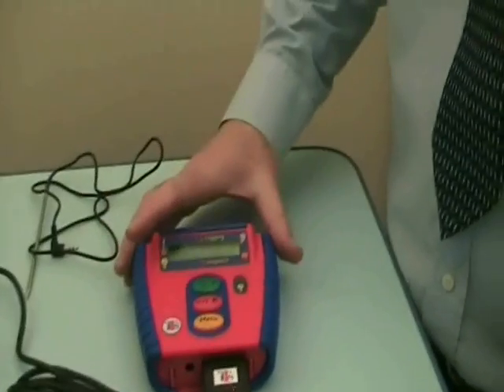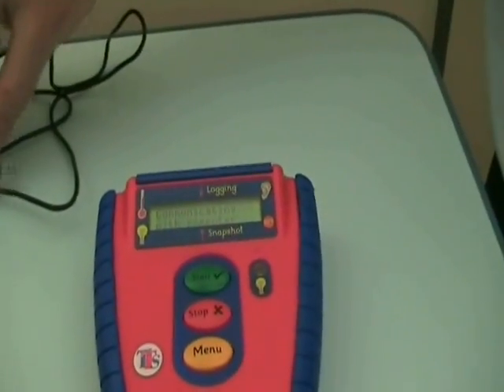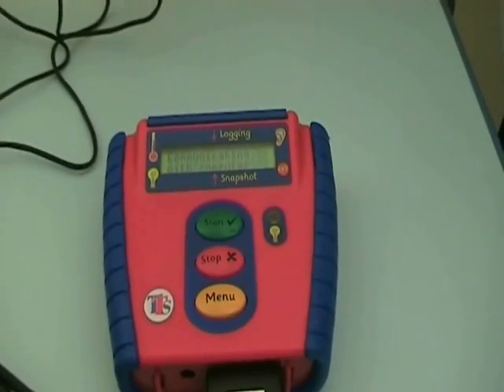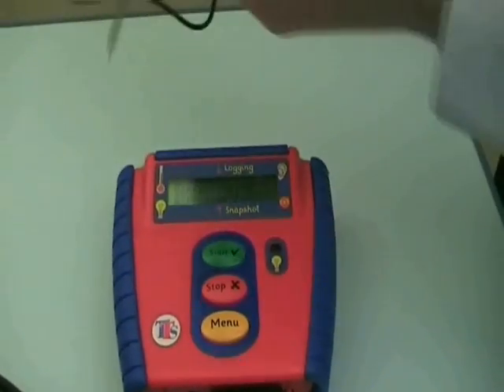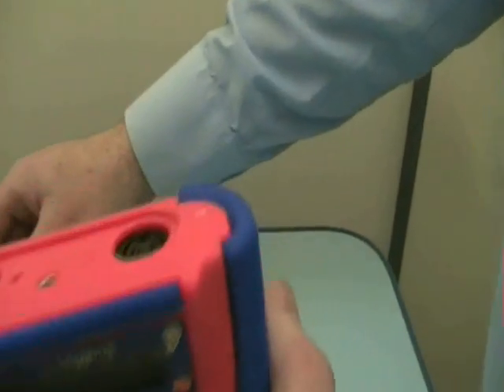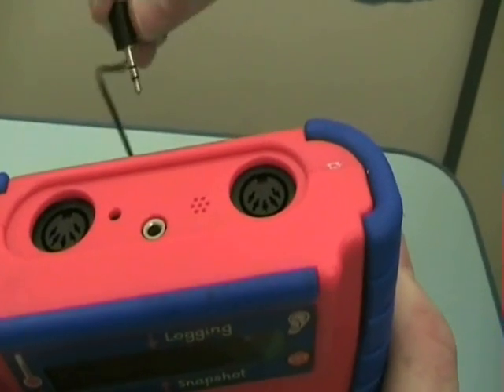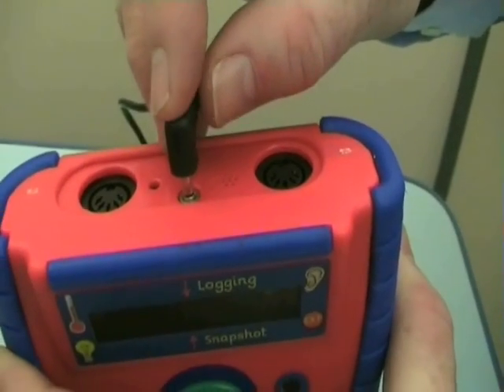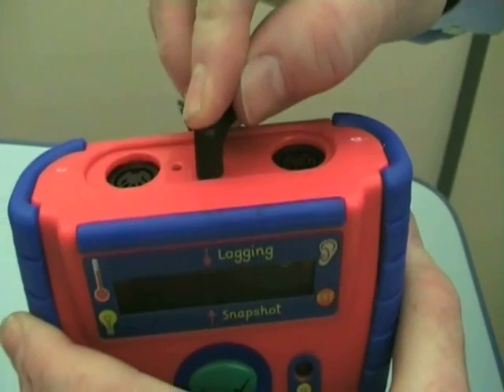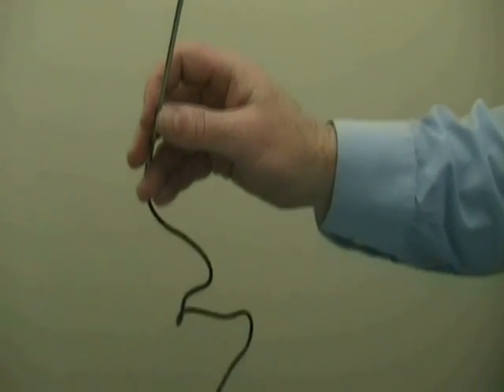With our logbox connected to the computer, we can position the temperature sensor away from the logbox by connecting an external probe into one of the sockets. At this moment, we'll use this center one which is replacing the internal temperature sensor. So if I plug in there, I now have a lengthy lead to a temperature probe.